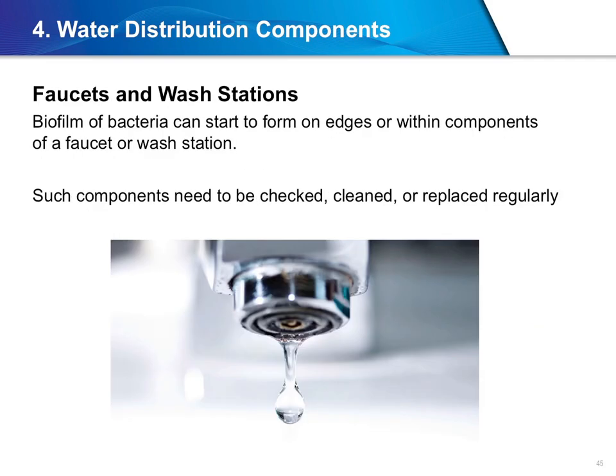Point-of-use fixtures are where people come in contact with water throughout the healthcare facility. The primary concern is that a biofilm can start to form on edges or within components of a faucet or wash station. If bacteria are allowed to build up in things such as aerators or faucet flow restrictors, it could grow and, worse, be sprayed into the air and cause illness. That means such components need to be checked, cleaned, or replaced regularly.